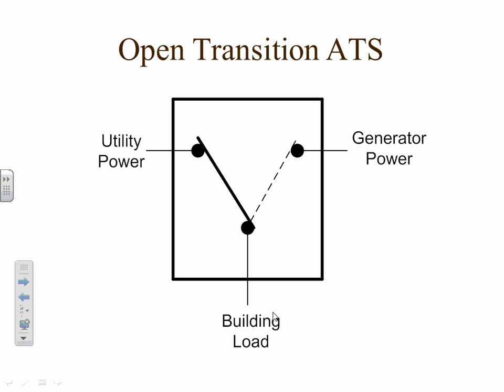The second one is used on non-legally required systems only. It's a time delay on transfer. So in other words, the sensors in this switch have seen utility power is gone on this terminal. It's the control of the transfer switch that tells the generator, hey, start. So it goes out and signals the generator, and this is done through the contacts and the control in the switch, which operates all the time whether there's power or not. So the generator set starts and comes up to speed and frequency, and the second time delay, like I said, is a time delay on transfer. What it's for is just to give the generator set a little time to run and stabilize before we transfer it from this position over to generator, before we hit it with a load, basically. So that's what that's for.